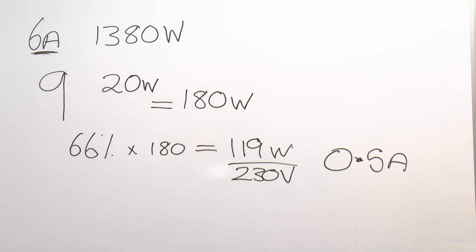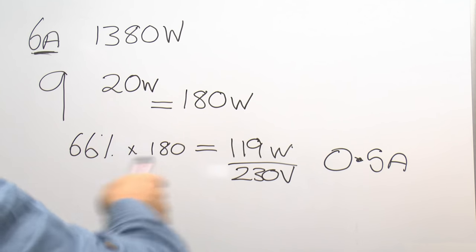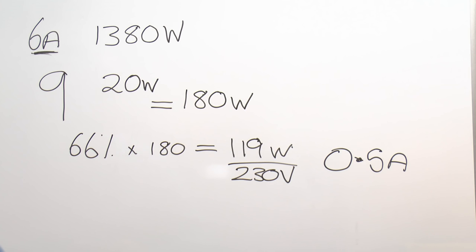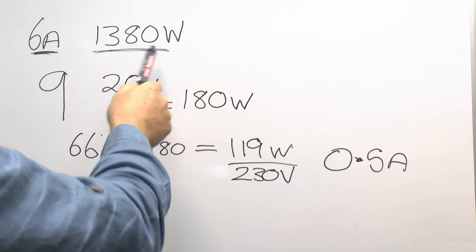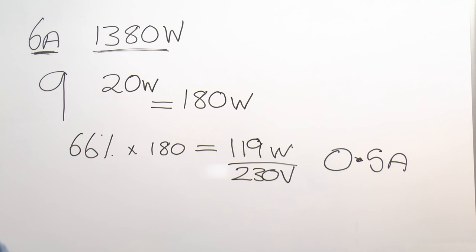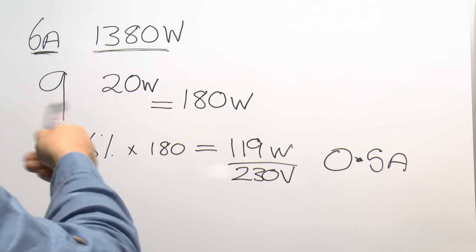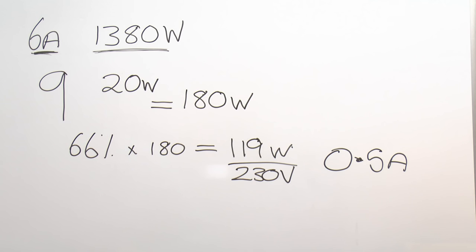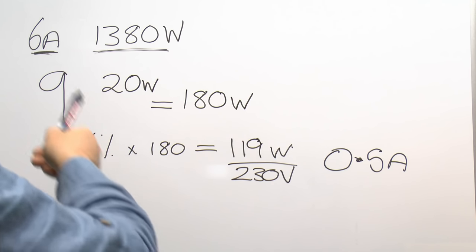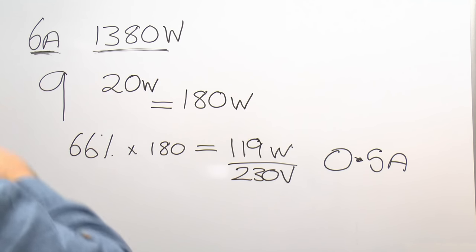This is just one example with a single pendant per room. Many properties have downlighters — the same principle applies: add up the fittings, estimate the load per fitting, total it, and take 66%. Halogen downlighters at 50W each — ten in a room — give 500W, which could approach the circuit limit. But LED equivalents at around 5W each mean ten in a room is only 50W. The answer is always going to be considerably less than the 1,380W or 6A you started with.